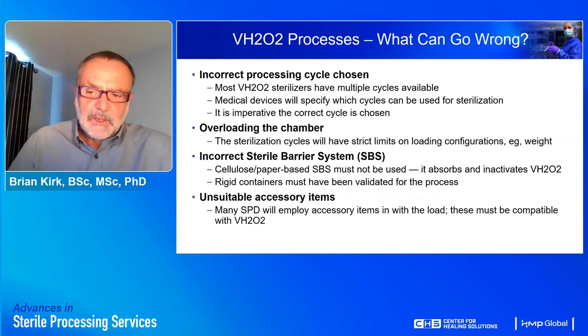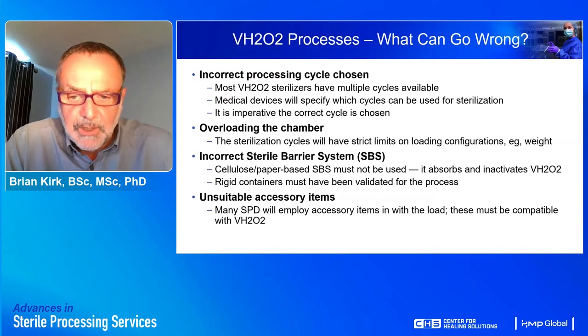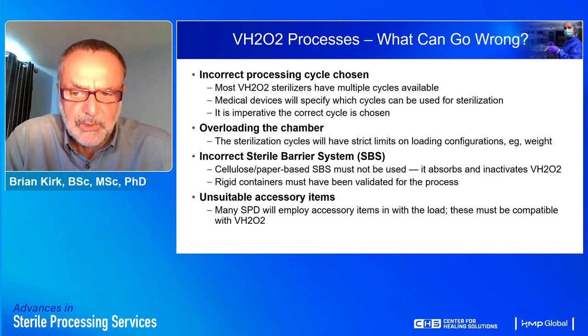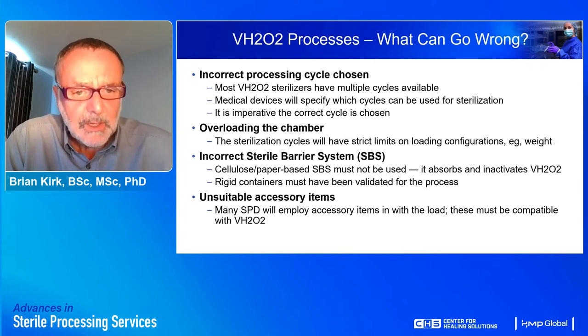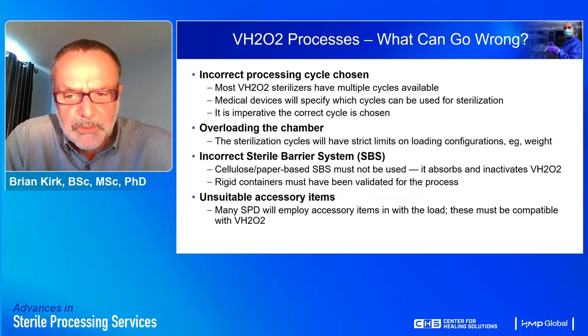Rigid containers can also be used, but they must be validated for use in the hydrogen peroxide process. Many sterile processing departments use accessory items within containers for ease of handling or positioning of instruments, but these should also be validated for use in the hydrogen peroxide process, because some materials like paper can absorb hydrogen peroxide and reduce its effective concentration available for killing microorganisms.